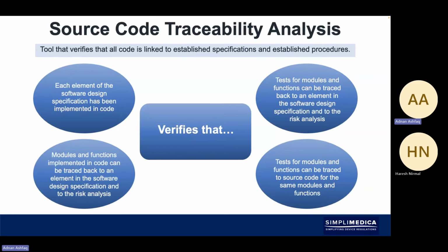So doing some kind of traceability analysis is also very important within the specification. So looking at the requirements specification, looking at the functionality specification, any design within the software, and then what testing you've done to make sure those requirements have been met. This is a very typical format in design development in medical devices.